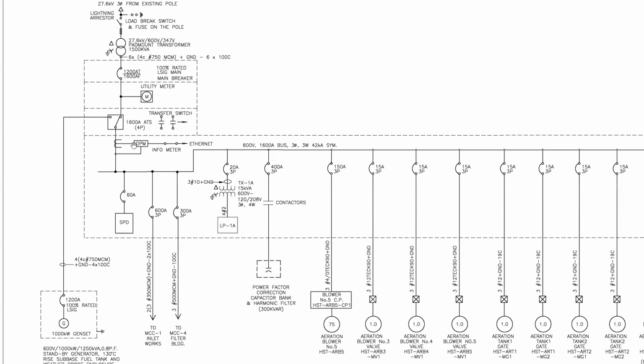Comes into here, this would be a power monitor. These are going to indicate some sort of CT or PT, so current transformer, potential transformer, to read power information coming into it. And it says Ethernet, so it's monitored by some computer somewhere.